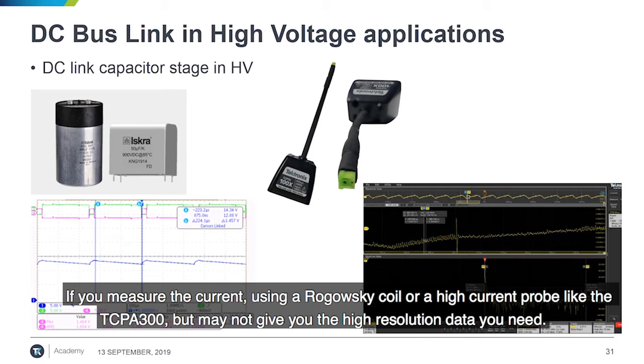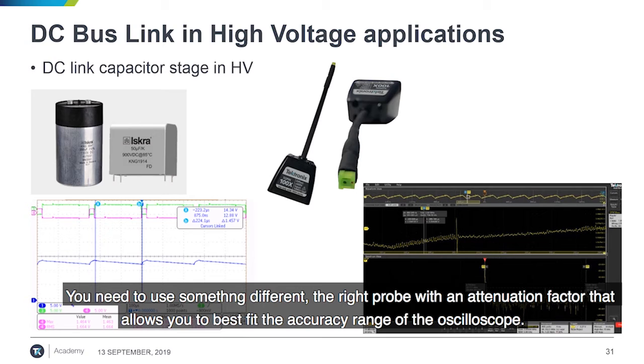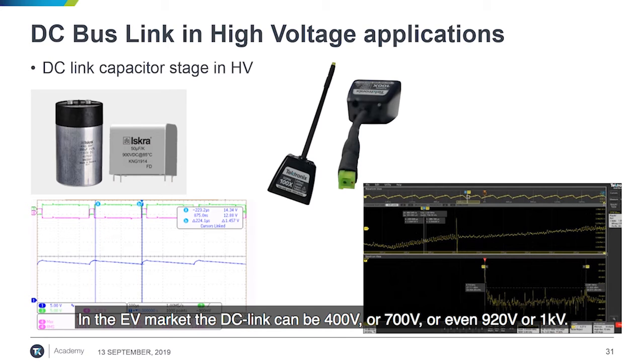If you measure the current, you may be using a Rogowski coil or a high current probe like the Tektronix TCPA 300, but this may not give you the high resolution data that you need. You need to use the right probe with an attenuation factor that best fits the accuracy range of the oscilloscope. In the electric vehicle market, the DC link can be 400 volts, 700 volts, even 920 volts, or 1 kV.